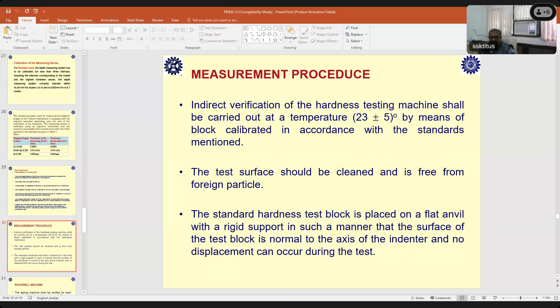In the Rockwell hardness machine, the testing machine shall be verified for each scale. Now, when you are verifying the machine, it is not sufficient to calibrate the machine for certain forces. You are calibrating the machine for all the forces. If you are using Rockwell A, B, C, then you have to calibrate the machine for the force applied for A and B and C. And similarly, if you are testing the machine indirectly, for verifying whether it is performing to expectation or not, then we have to verify it in all the scales. That is preferable.